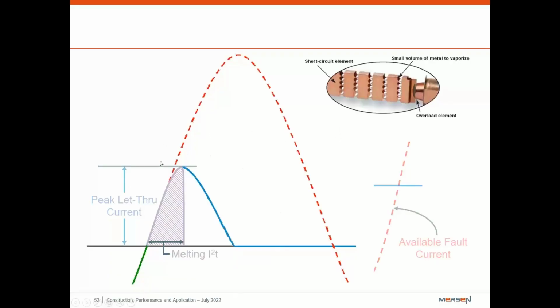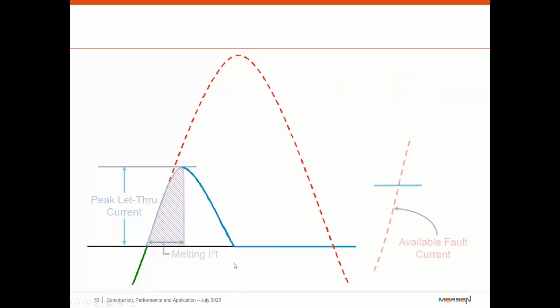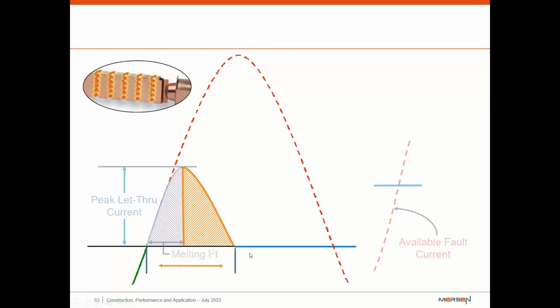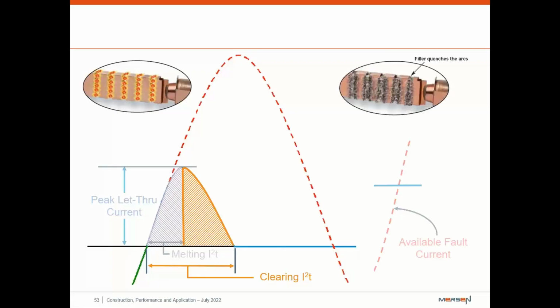The first half of this is going to be known as the melting I squared T. It's how much energy is going to be flowing through the element. It's going to jump across all these holes, vaporizing all that material, and essentially coming in contact with that filler. Once it does, the second half of this is going to be the clearing I squared T, which is how much time it takes to vaporize that material, come in contact with the filler, and turn into an insulating material. So now you can see this is what that sand will actually look like, or the magic that happens inside of this fuse.